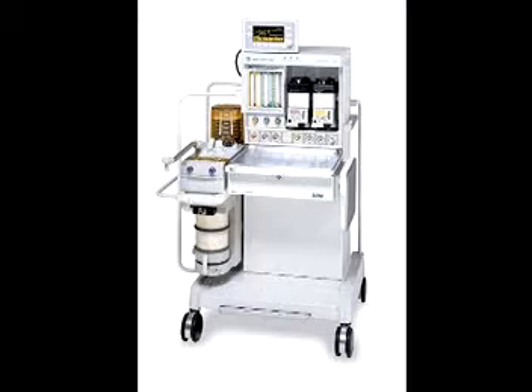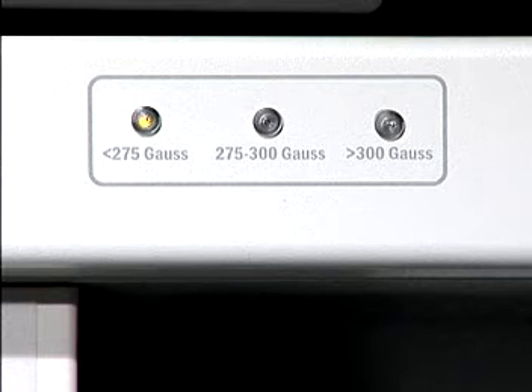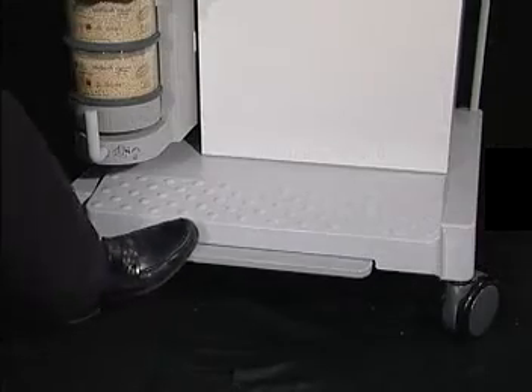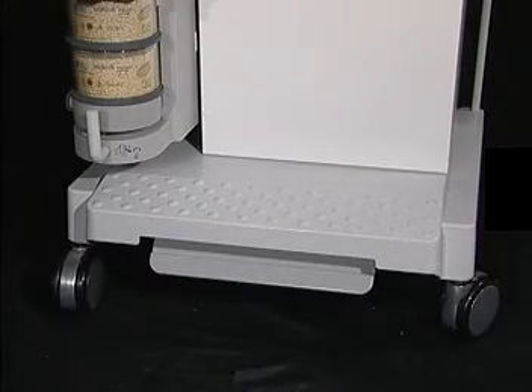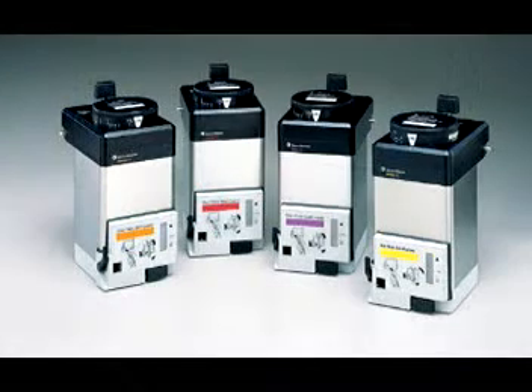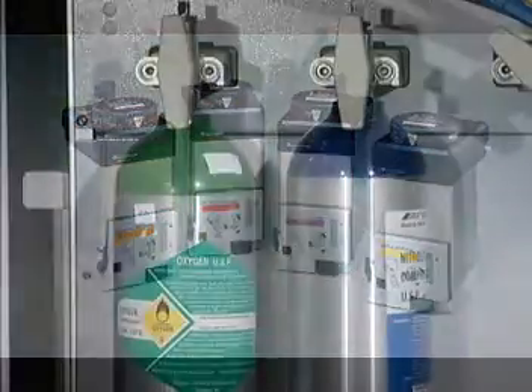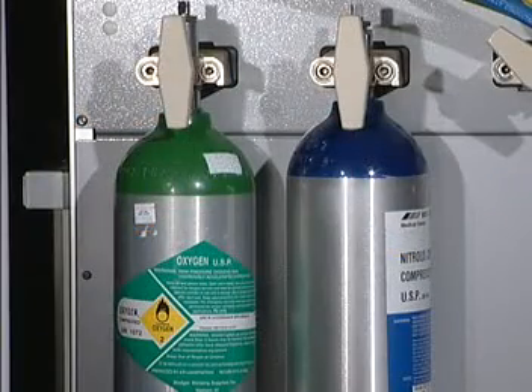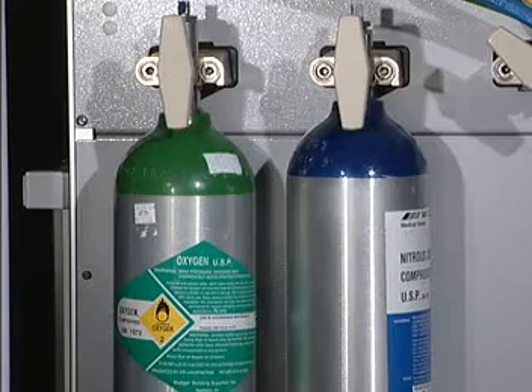The MRI variant of the Aestiva line is compatible to the 300 Gauss line, and a monitor is provided to alert the operator if the machine is too close to the MRI magnet. There is a minimal amount of ferrous material in the machine, so setting the brake is necessary to avoid the machine creeping toward the magnet. All Datex-Ohmeda vaporizers are compatible with the exception of the Desflurane Tec 6. Only aluminum cylinders should be used in the MRI suite.